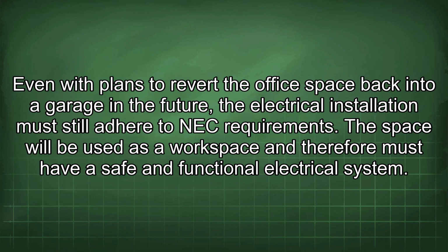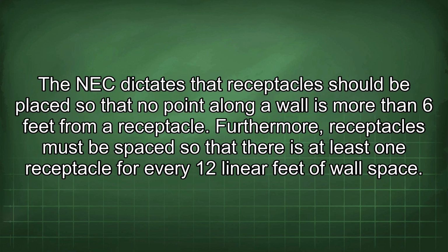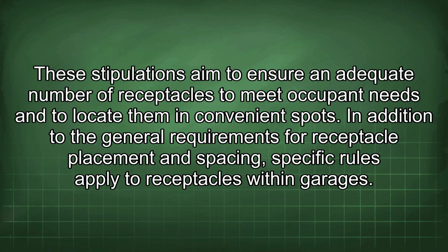electrical system. The NEC dictates that receptacles should be placed so that no point along a wall is more than 6 feet from a receptacle. Furthermore, receptacles must be spaced so that there is at least one receptacle for every 12 linear feet of wall space. These stipulations aim to ensure an adequate number of receptacles to meet occupant needs and to locate them in convenient spots. In addition to the general requirements for receptacle placement and spacing, specific rules apply to receptacles within garages.